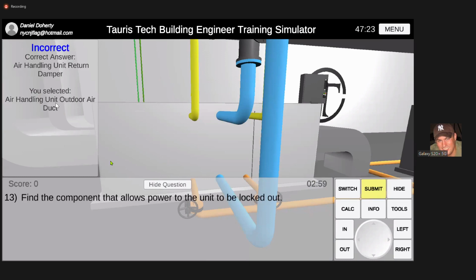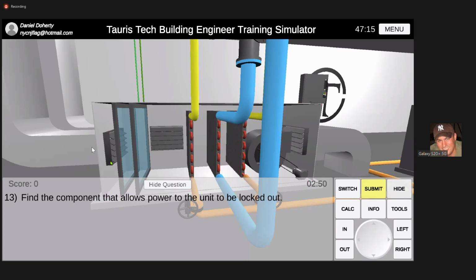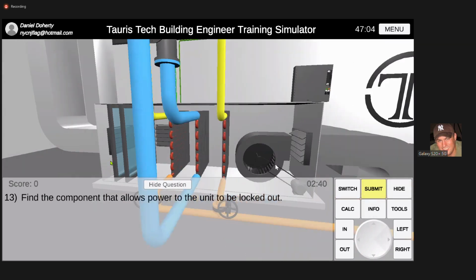You selected air handling unit outdoor air duct. So that's the outside air coming into the unit right here. And I guess the question should have been, what is the tip for you to know that that's the return? How do I know that the other one's a return? Look at the way that the fan's facing. The fan's facing the supply air duct, right? It's taking air in, the squirrel cage is spinning, and it's shooting the air out through the supply air duct.